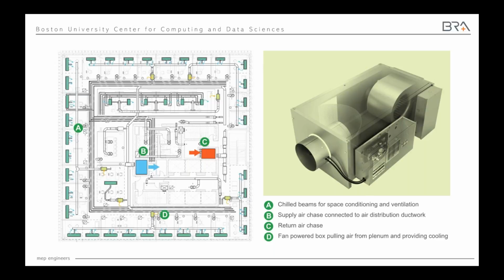So instead, what we did was we added these fan-powered boxes that sit between the air handler and the chilled beam, and they decouple those two things so that you can ventilate just as much as you need to, and you can heat and cool just as much as you need to by blowing air through the fan-powered box. And what that gets you is an ultra-low energy design, but also low maintenance, right? Because you don't have 30 fan coil units all over the space. You have just 7 of these fan power boxes per floor that then distribute out to all the chilled beams.